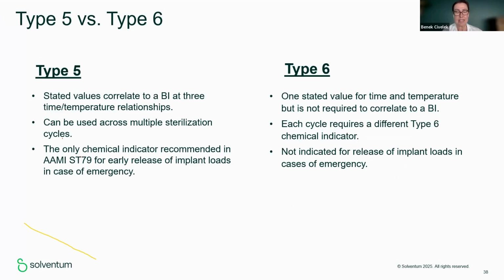Type 5 doesn't have any elimination or limitation. It can be used across multiple cycles, but for each cycle you need a different type 6, confirming this time and temperature. When you look at AAMI ST79, it is clearly stating that for early release of implant loads, in case of emergency, type 5 is needed, even needed in a PCD together with a BI. But for type 6, we don't have such a requirement.